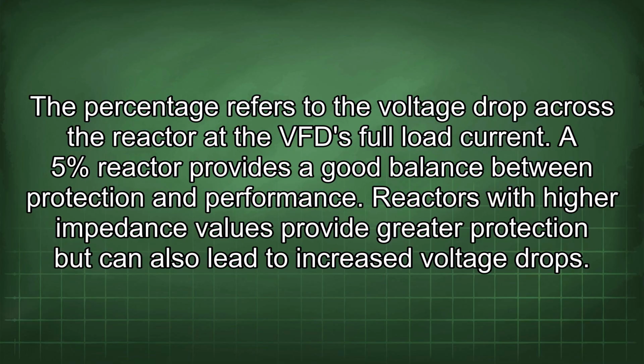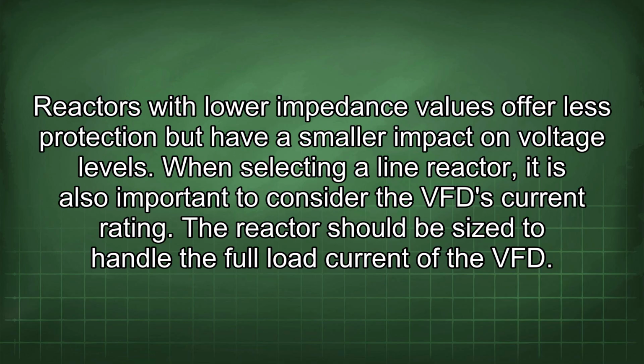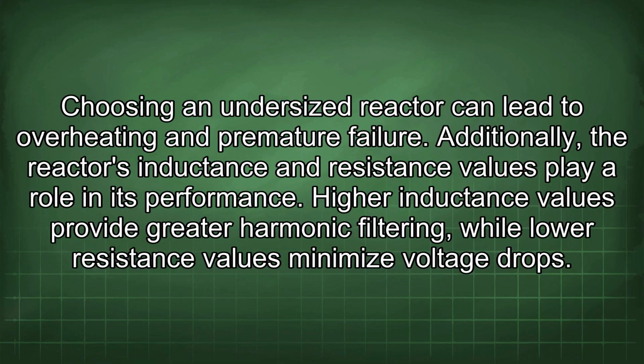Reactors with higher impedance values provide greater protection, but can also lead to increased voltage drops. Reactors with lower impedance values offer less protection but have a smaller impact on voltage levels. When selecting a line reactor, it is also important to consider the VFD current rating. The reactor should be sized to handle the full load current of the VFD. Choosing an undersized reactor can lead to overheating and premature failure.